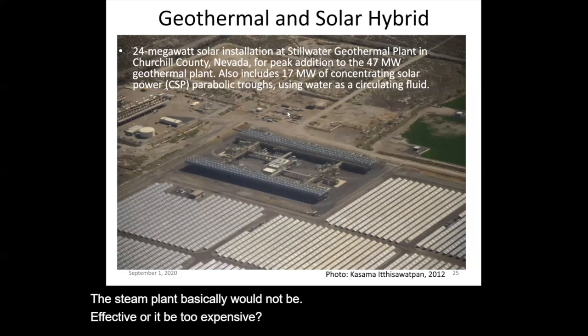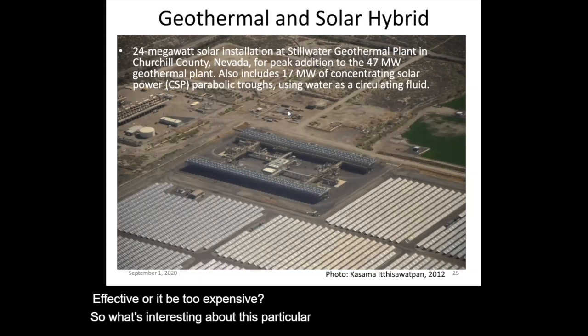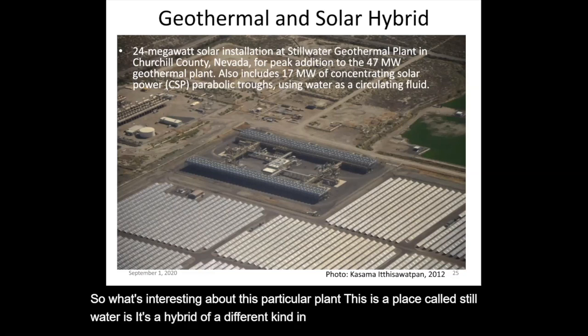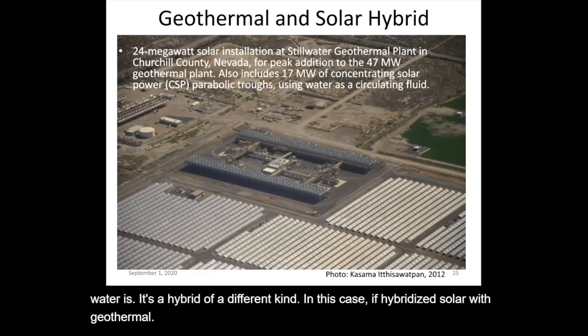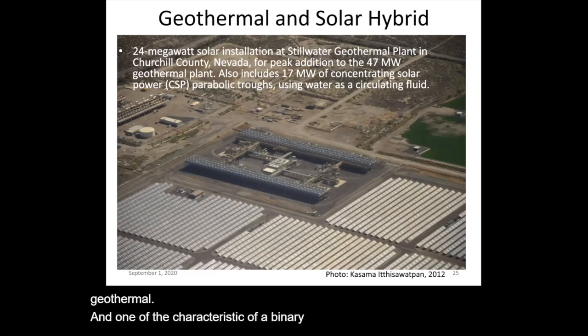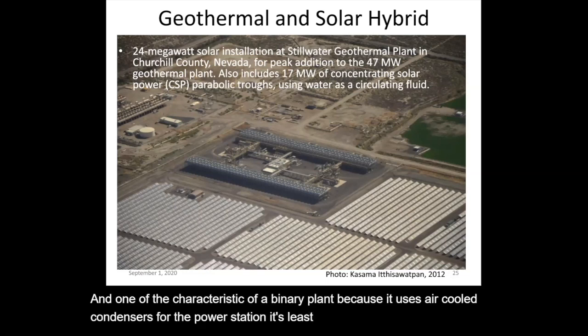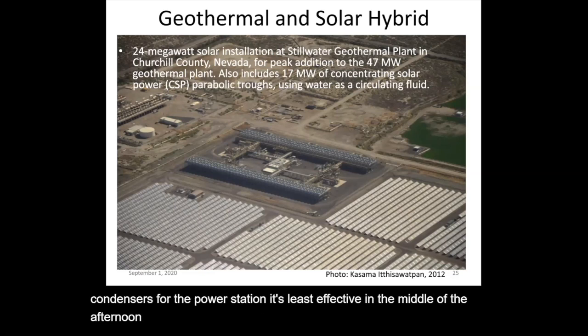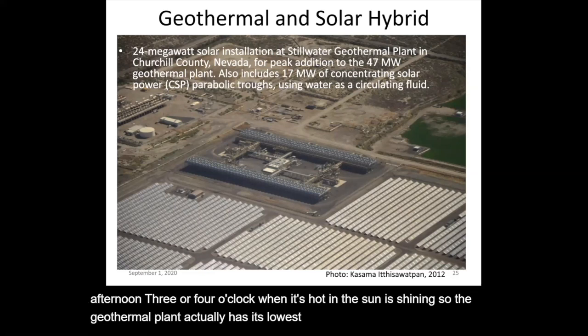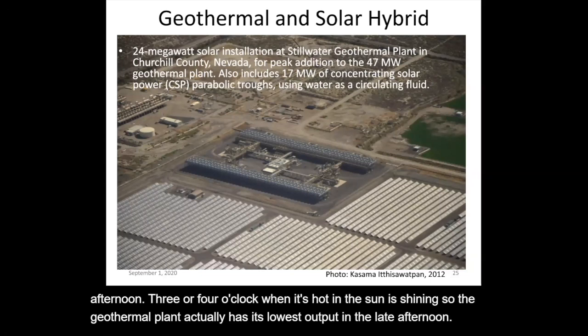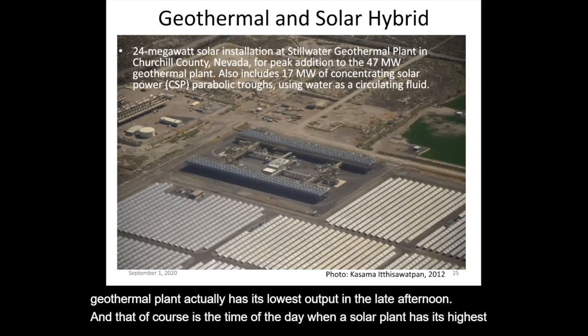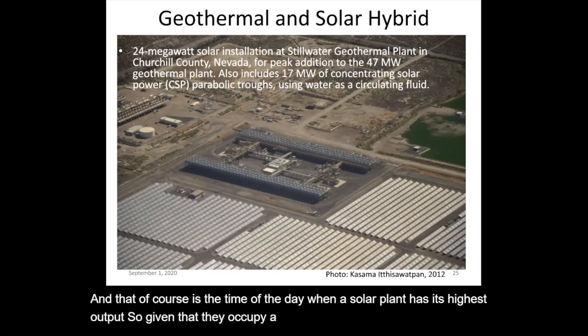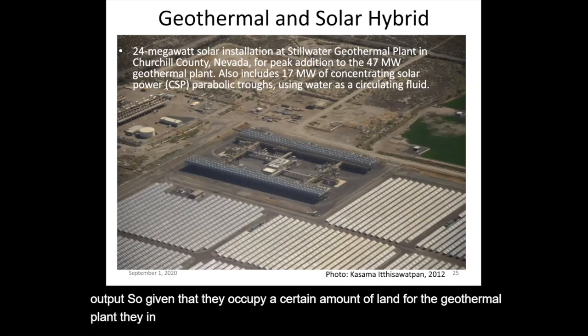This particular plant, called Stillwater, is a hybrid of a different kind: they've hybridized solar with geothermal. One characteristic of a binary plant is that because it uses air-cooled condensers, it's least effective in the middle of the afternoon, 3 or 4 o'clock, when it's hot and the sun is shining, so the geothermal plant actually has its lowest output in the late afternoon. That's exactly when a solar plant has its highest output. So given the land already occupied by the geothermal plant, they've added solar PVs.